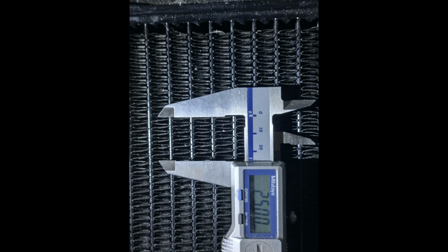As you can see in the photo, this is how I calculated fin count per 25 millimeters: by simply placing a vernier caliper set at 25 over the core and then taking a photo, counting the number of fins between the calipers. We also measured the tube width, which is perpendicular to the jaws of the caliper, at 2.3 millimeters. The number of tubes: there's one tube behind the other in this case, consisting of 2 rows, and the profile of that tube was approximately 12 millimeters.